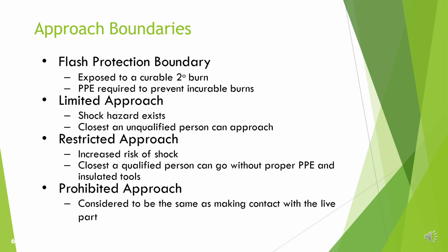So when we're determining approach boundaries, we need to look at the actual circuit, or where the source of power is, and imagine rings or different stages around that in a circular fashion. The very outer band, or outer ring, we're going to call the flash protection boundary. This is where you can be exposed to a curable second-degree burn, but we still have to have PPE required to prevent incurable burns. That's why anyone within that flash protection boundary will need to have the basic PPE ensemble.